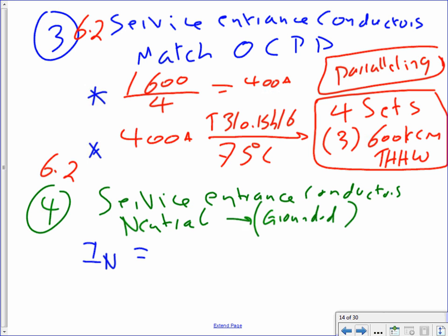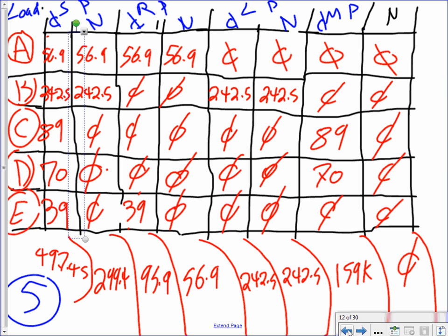I want to remind you guys of the neutral load. Let's go back and look at the neutral load that you guys calculated. There you go. Can you guys see the neutral load? 299.4. So that's the number they're going to use.